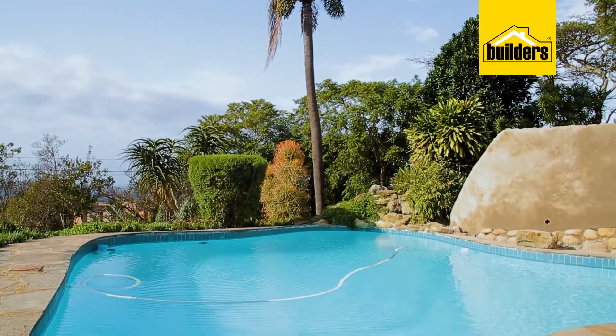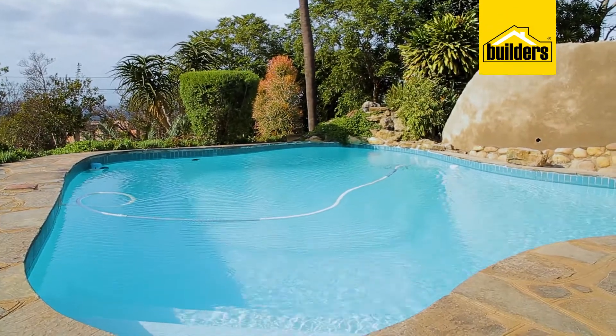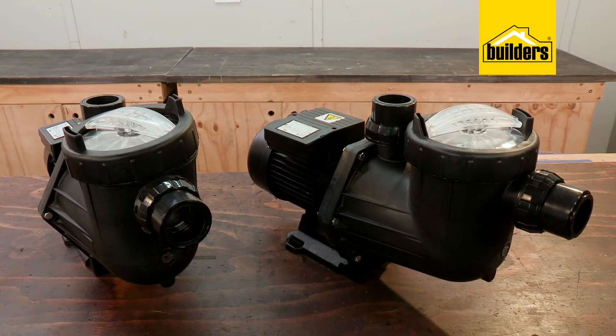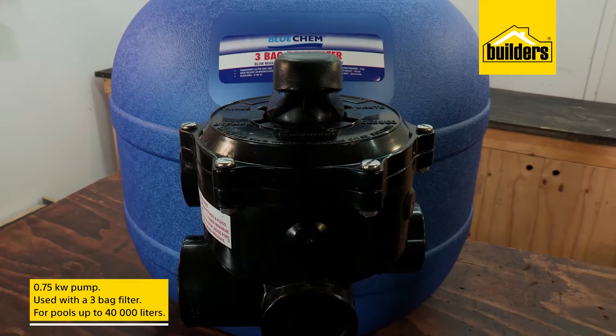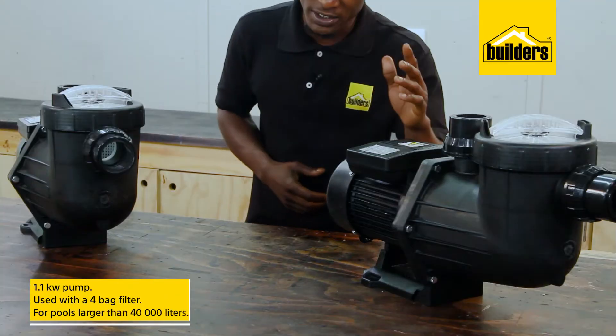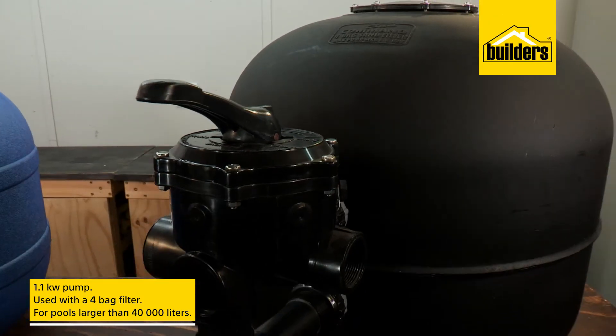The majority of pools will fit into the small to medium or medium to large category. Here are two of the pumps in the Blue Chem range that are stocked by Builders. The 0.75 kilowatt pump is designed for use with a three-bag filter and for pools of up to about 40,000 liters. For pools larger than this, the 1.1 kilowatt pump is suited and this pairs with a four-bag filter.